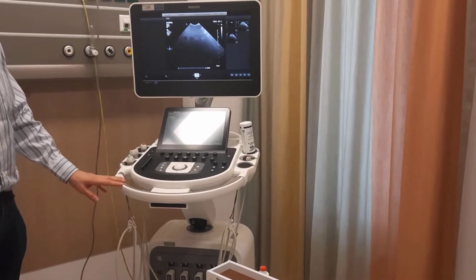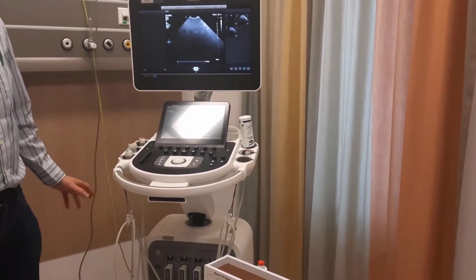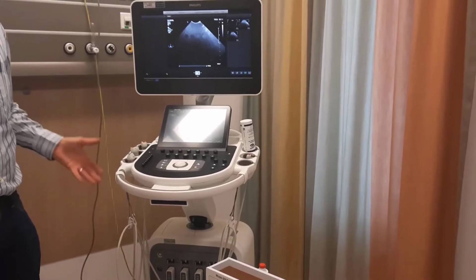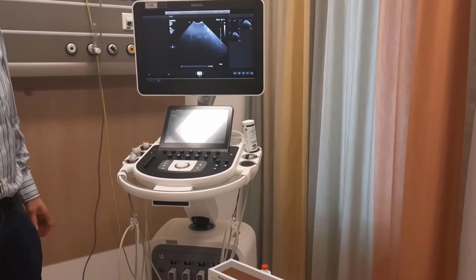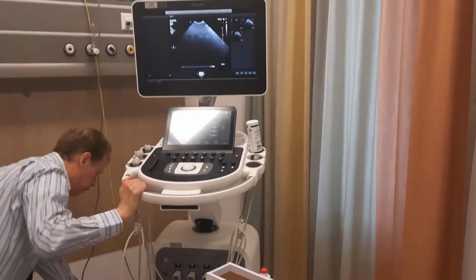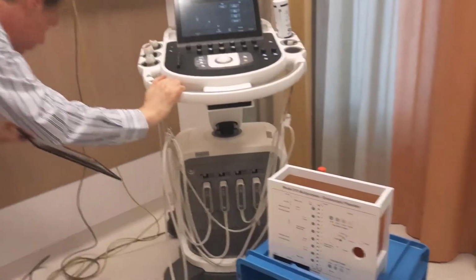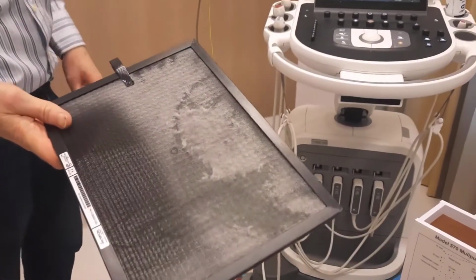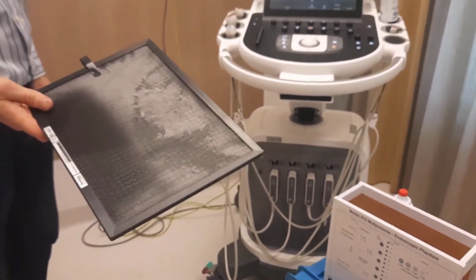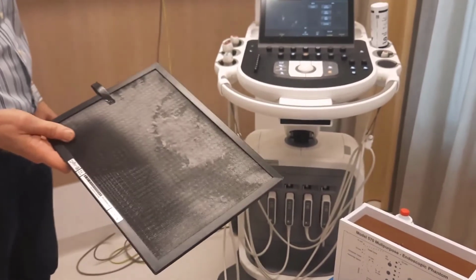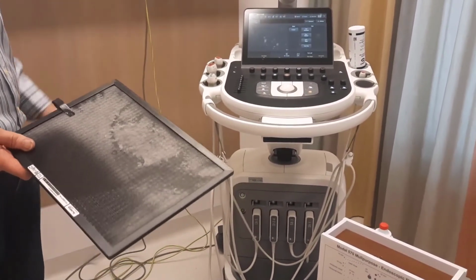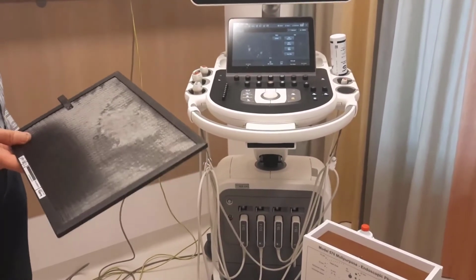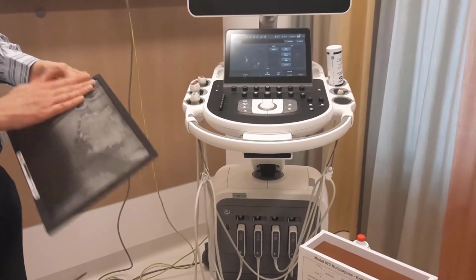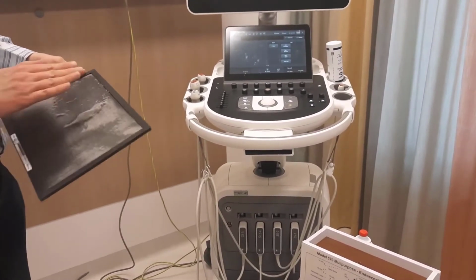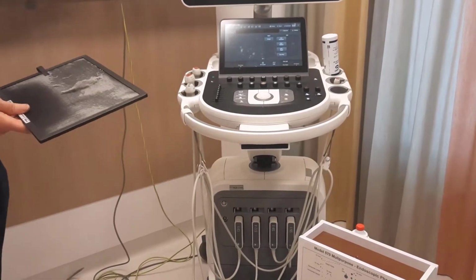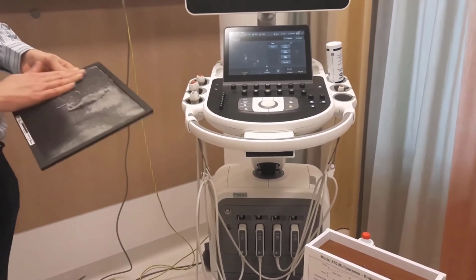Almost every ultrasound machine has a ventilator in the power supply. The power supply gets hot and it has a ventilator to cool it down. Before that, there is a big filter to prevent dust coming into the machine. And we have to clean this twice a year. Even in a hospital, which is a clean environment, it gets dirty very quickly, and then we have to clean this. And if you don't have air pressure, you can clean it by hand or with a vacuum cleaner.